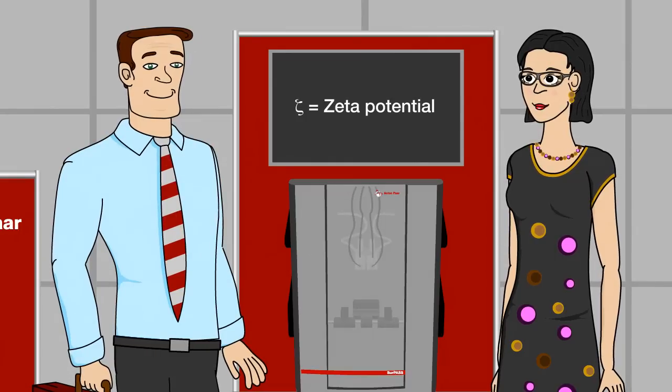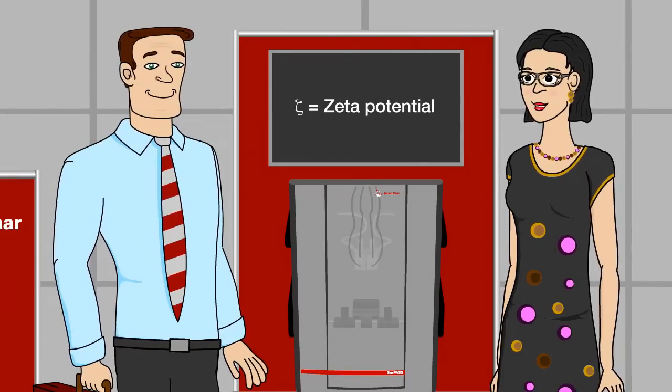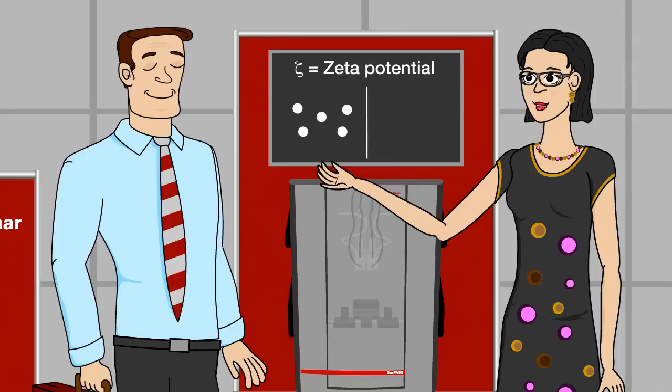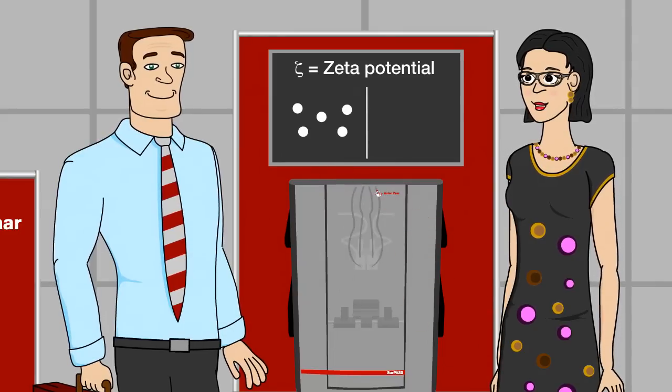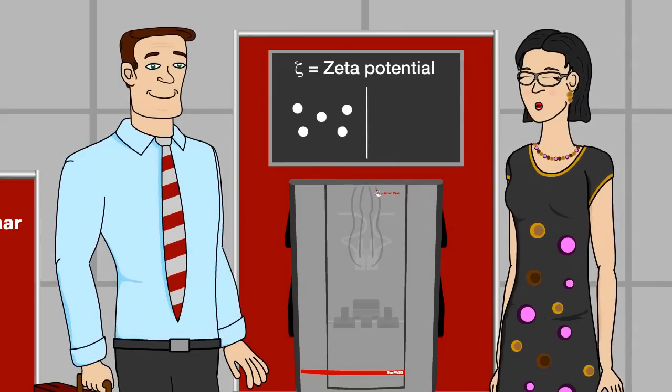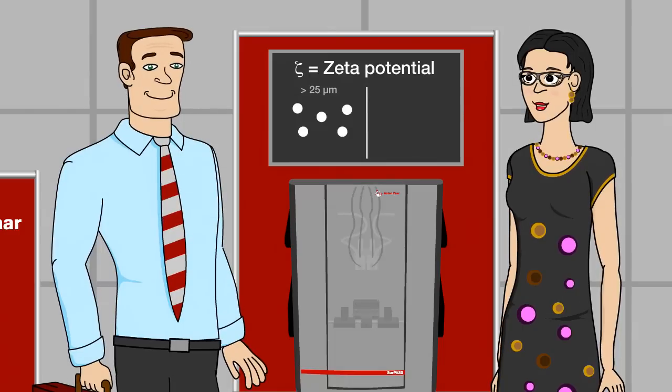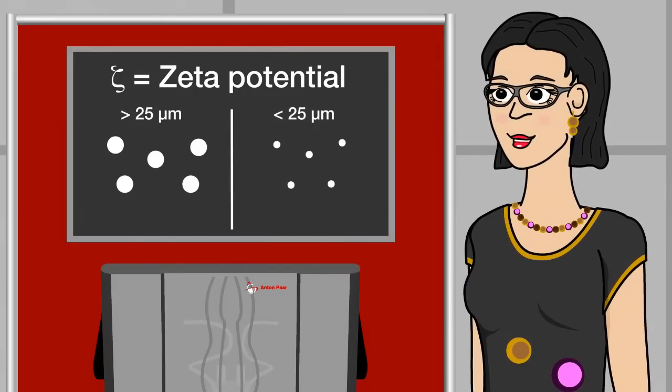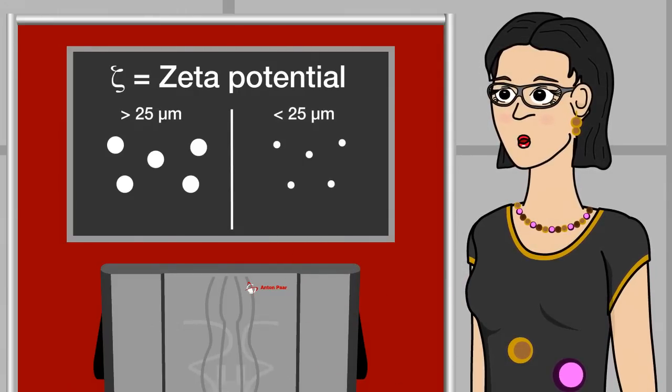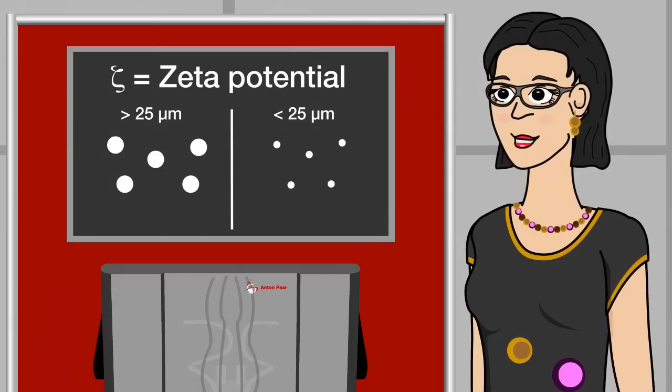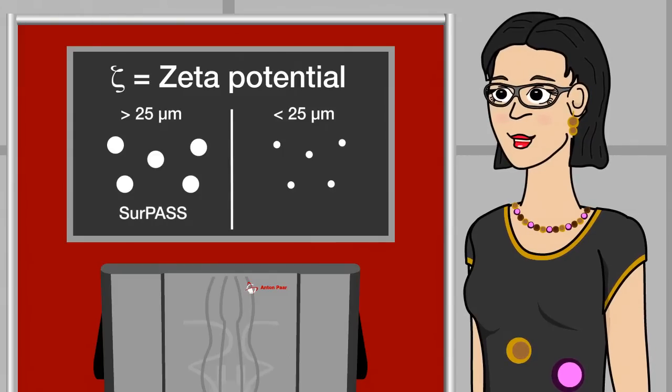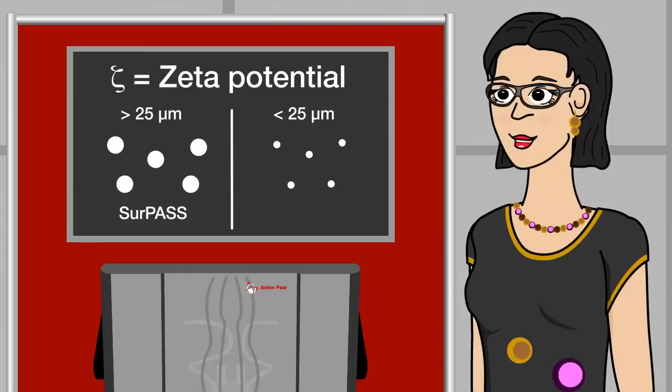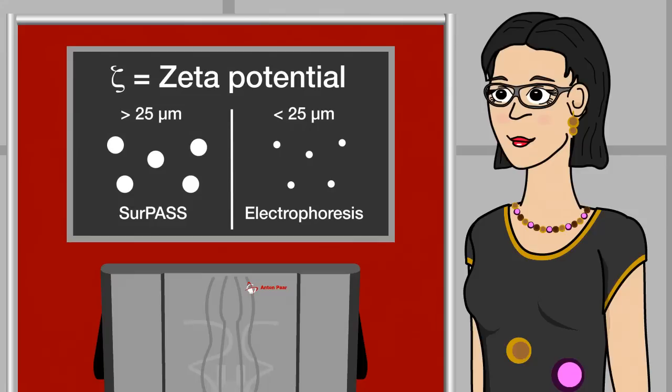Exactly. Oh, but let's be precise so that there is no misunderstanding. Imagine two different groups of samples. Here we have macroscopic solids of any shape, like plates, foils, fibers, granulates or powders with particles larger than 25 micrometers. And here we have particles which are smaller than 25 micrometers. If you want to analyze the zeta potential of macroscopic solids, you use SURPASS. If you want to analyze the zeta potential of smaller particles, you use an entirely different method, electrophoresis.